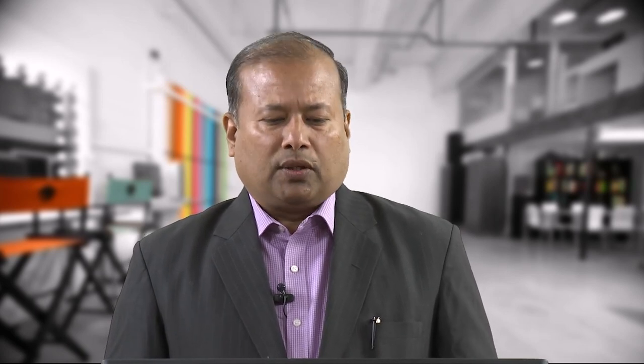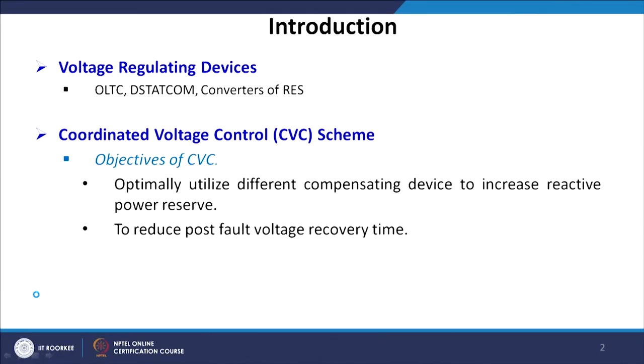Focusing on coordinated voltage control, the main objective of the CVC is to optimally utilize different compensating devices to increase reactive power reserve. The objective is to increase the reactive power available within the system to take care of voltage control. Additionally, we aim to reduce the post-fault voltage recovery time with the help of the CVC scheme.